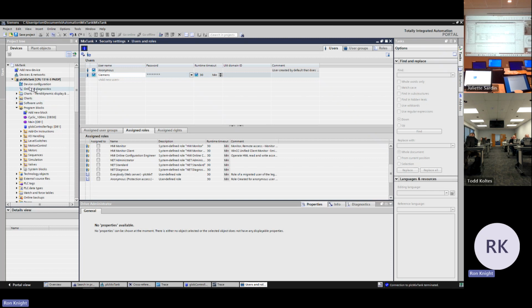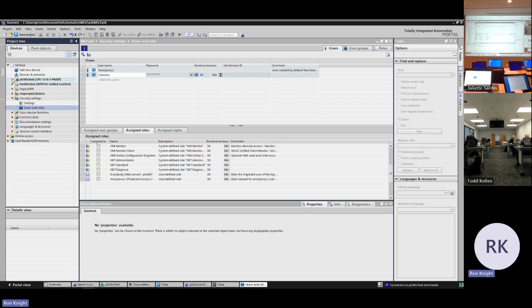What iDevice allows you to do is add a PLC that looks like an IO device to another PLC. And so now you can just exchange data between the I and Q tags. And you can pass UDTs the same way. You just serialize the UDT into a bunch of bytes and send it across IO. So you're doing it at IO speeds.